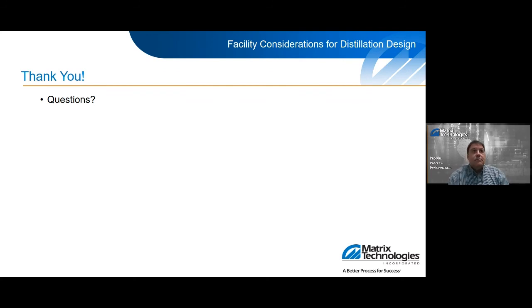All right, next question is, should you consider hose stations or fire monitors with new construction? I would say no. The reason for that is you really need to train your facility or your operators to be able to fight the fire, and most companies don't really have an on-site fire brigade that would do that. So if you were to put those in there, you need to have people trained to use it, and the fire department's not going to use it because they don't know if it's been maintained and the serviceability of it as well. So I would shy away from doing that because it's probably not going to be used by the fire department, and you're not going to want to train your staff unless you have a very large facility that you need to do that at.